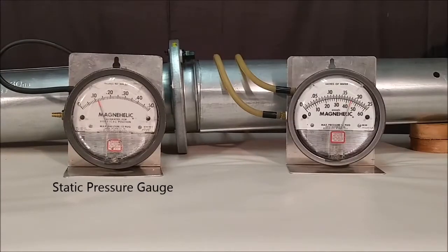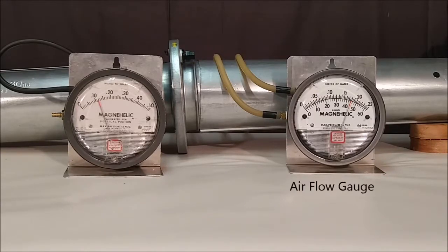This fan is running in an almost wide open condition right now, where the static pressure is running at 0.1 of an inch, which is the pressure needed to overcome the resistance of the ductwork and the turbulence of the measuring section. It's close to wide open condition, but already you can see that 0.1 of an inch is still 50% of the allowable 0.2 that is written into the BC Building Code.